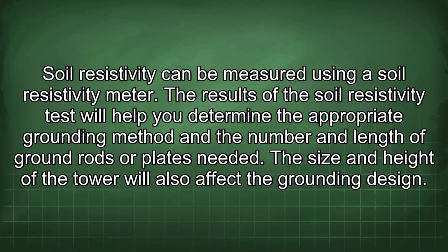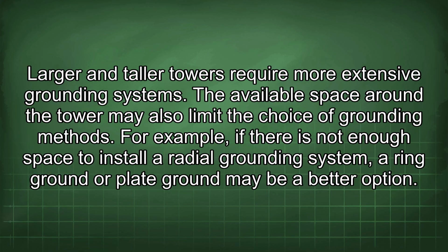The size and height of the tower will also affect the grounding design. Larger and taller towers require more extensive grounding systems. The available space around the tower may also limit the choice of grounding methods. For example, if there is not enough space to install a radial grounding system, a ring ground or plate ground may be a better option.